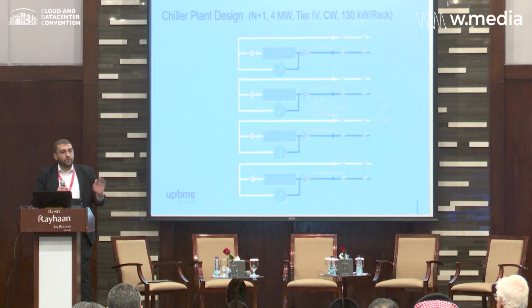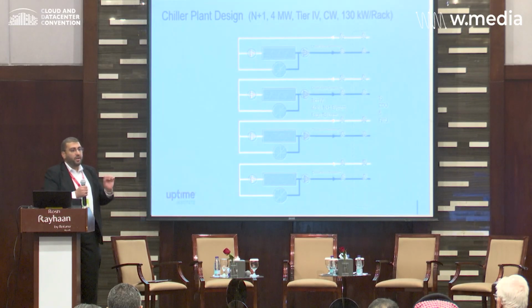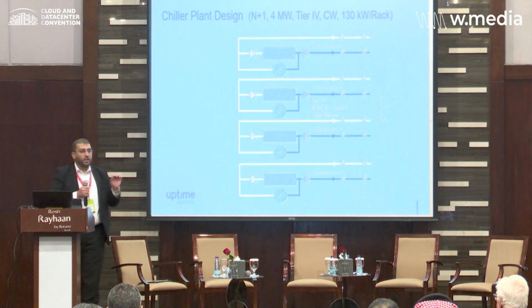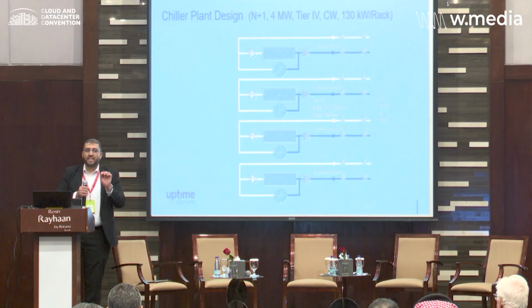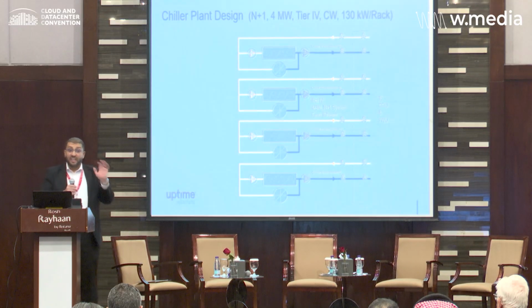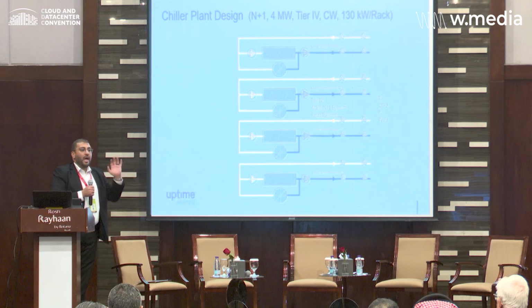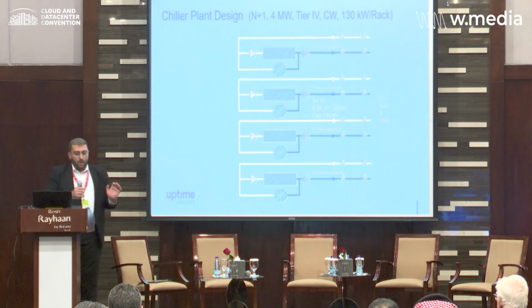In addition to that, there is a set of motorized valves which act autonomously in case of a leak. In case there is any leak, those valves will detect, isolate and close, and sustain the AI workload.